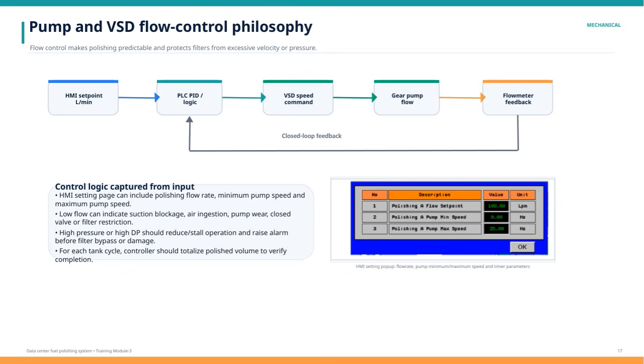This creates a closed-loop feedback system that continuously monitors and adjusts flow to keep the operation within safe and efficient parameters. If the flow is too low, it may indicate problems like suction blockage, air entering the pump, wear, a closed valve, or filter restriction.